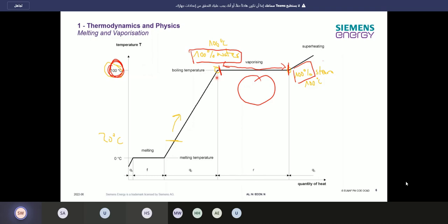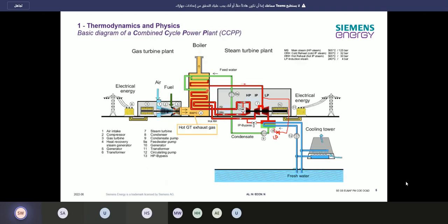And then when we go further, we're coming here to the evaporator. We have the drum, we have the evaporator, and the evaporator is designed for the evaporation process. Because what's happening, I have a water volume in there, and the water is steaming out. I'm getting a much bigger steam volume in there, and the steam volume needs to be there so that the piping can handle it.